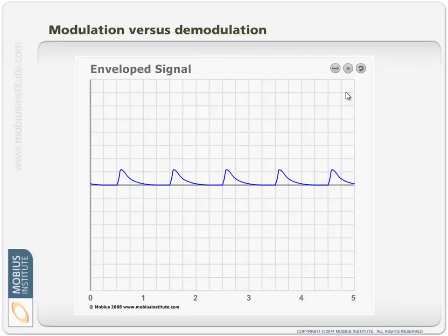So it can be confusing. We can say, well, isn't the signal the same as just the vibration? No, it's not. There's a number of reasons, but really what we're doing is we're taking advantage of the fact that the bearing resonates, or the sensor resonates, or we can pick up the stress waves. We can use some signal processing to detect those very short duration peaks or impacts, whatever you want to call them, and then going through this so-called demodulation process, we make them visible in a spectrum or a time waveform. So it's a very effective technique.